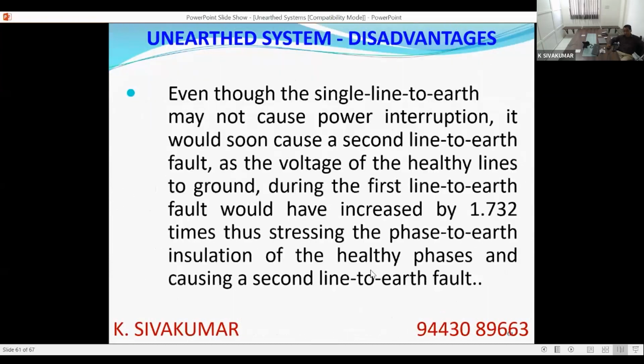Next, we said that there will not be any power interruption during a single line to ground fault. So it is a big advantage. Practically, it is not so. Even though the single line to earth fault may not cause a power interruption, it will cause a second line to earth fault sooner than later, because the ground potential has now become phase potential during a single line to ground fault. Then the second phase and the third phase to earth voltage has increased, and their insulation will be stressed. So sooner than later, a second line also will get grounded. There have been instances of immediate second fault in the system.